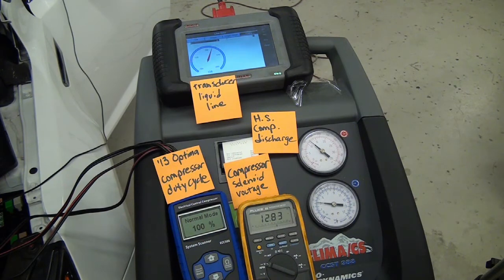Well, that didn't take that long, only a couple minutes, and it looks like we've pretty much hit the top. The compressor is being commanded at 100% duty cycle, which is coming out to about 12.87, maybe 12.9 volts. There's been very little change to the low side. Looks like it's at about 41 psi.